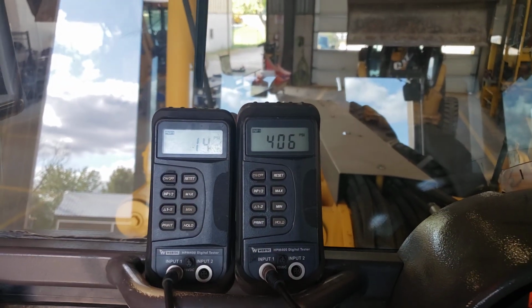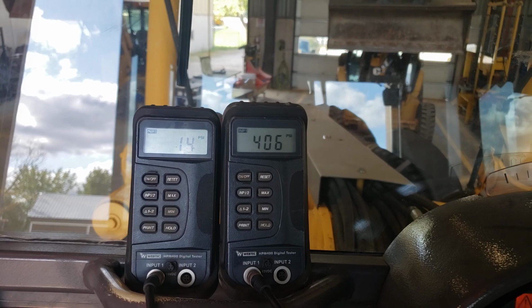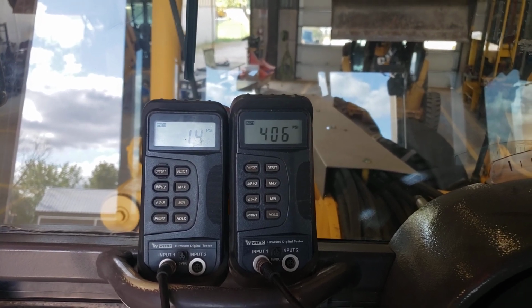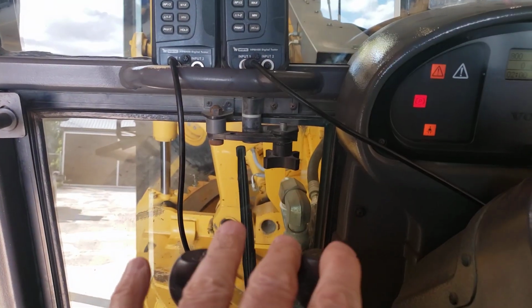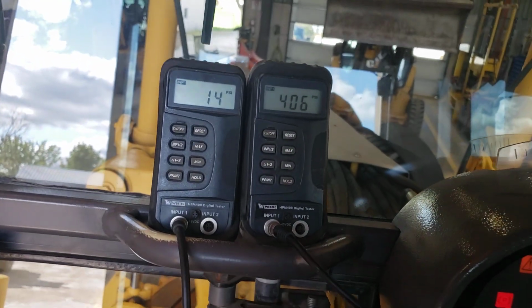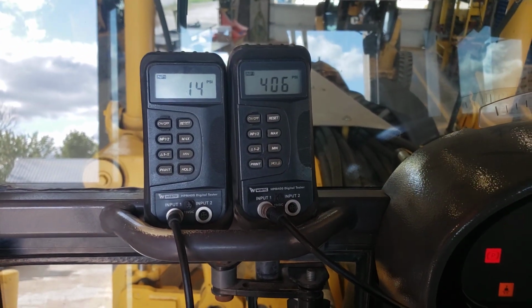So I'm reading about 14 psi on my load sense signal. I'm not sure why that is. I would expect 0 when I'm not using any controls. But something's bleeding through a little bit in that valve and feeding a little bit of a signal out.